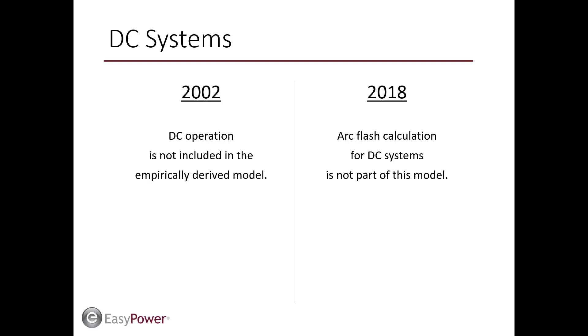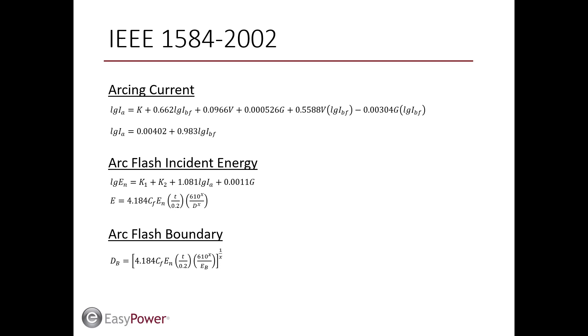DC systems remain unsupported in the 2018 standard, with only slightly revised language. Regarding the calculation formulas: the 2002 standard used a small set of equations — low and medium voltage equations for arcing current, an incident energy equation converted from normalized, and an equation for arc flash boundary. For 2018, the quantity and complexity of the equations is greatly increased.